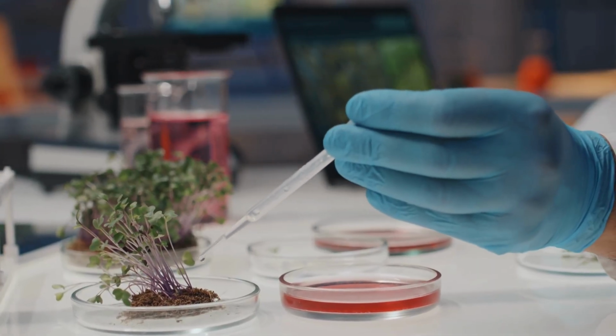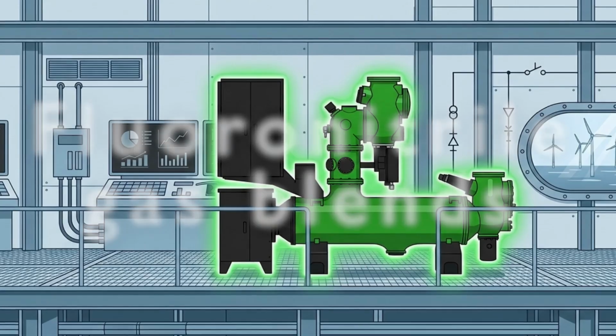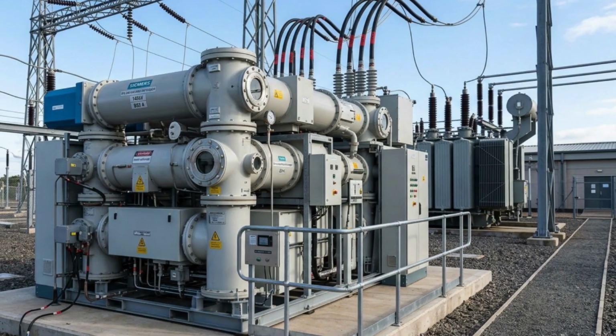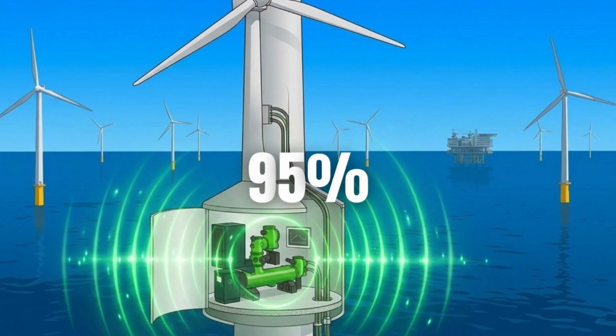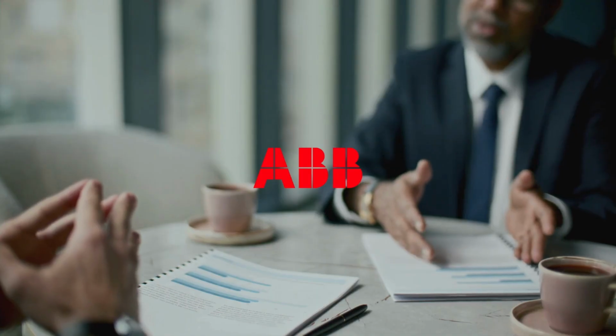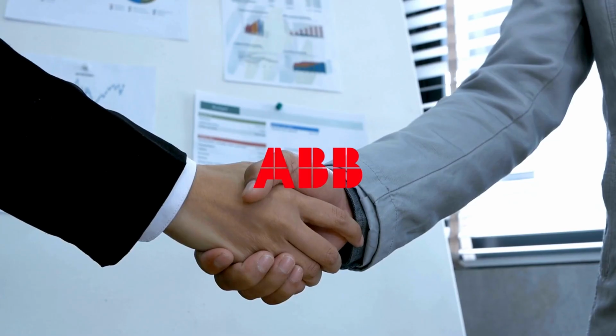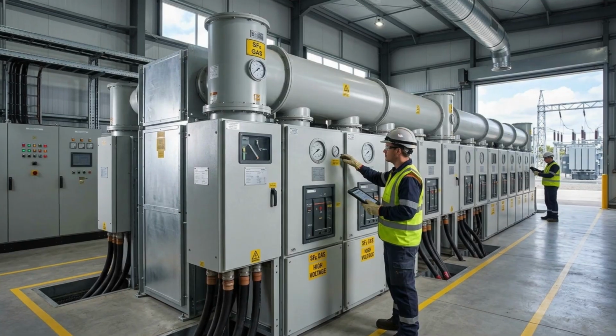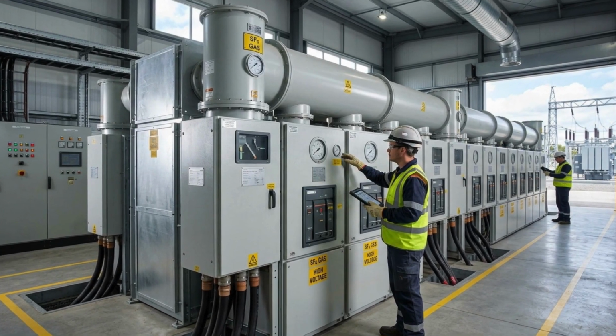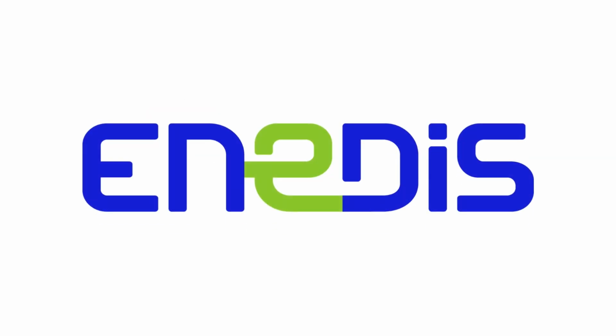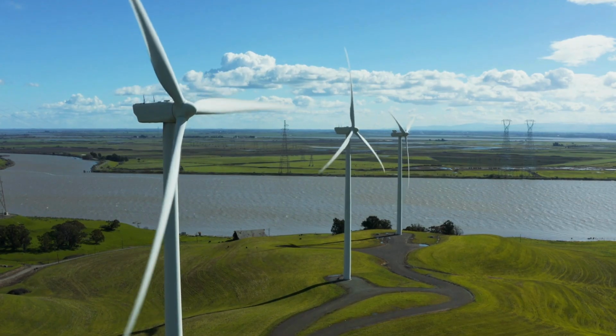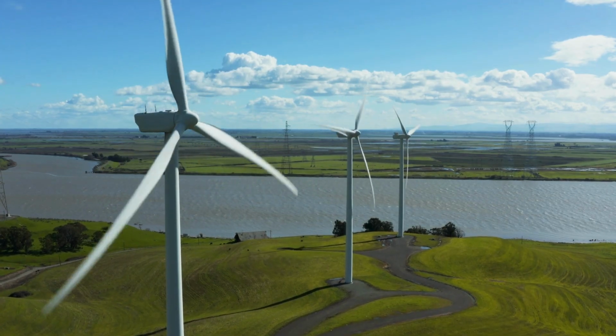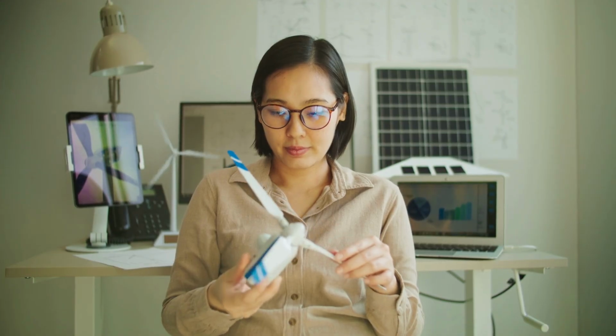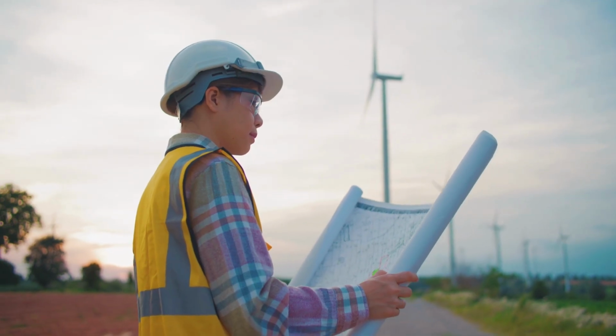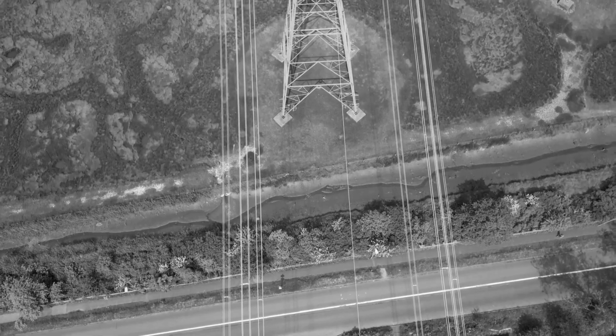Other giants have taken alternative routes. General Electric has deployed fluoronitrile gas blends that perform identically to SF6 but reduce the carbon footprint of the equipment by 95%. Meanwhile, ABB has secured framework agreements to supply solid insulated SF6-free switchgear to major European distribution networks like E.ON in Germany and Enedis in France. For the tens of thousands of older turbines already spinning with SF6 inside, the transition remains practical. The new regulations do not force developers to prematurely rip out functioning switchgear, which would trigger massive grid downtime and tons of premature electronic waste.